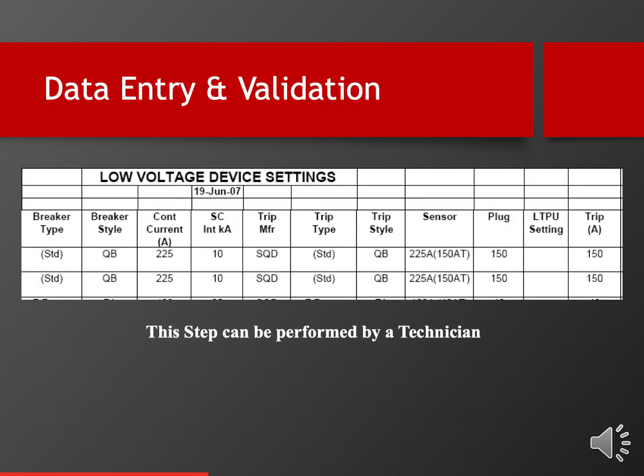What you see in front of you is a low voltage circuit breaker spreadsheet. One of the wonderful elements of an arc flash risk assessment study is these spreadsheets have all of the information you would need if, for example, you blow up a circuit breaker and it is unidentifiable what was there. You can look at the spreadsheet to find out what was there exactly: the make, model, style of everything, the trip settings, everything is available to you right there.